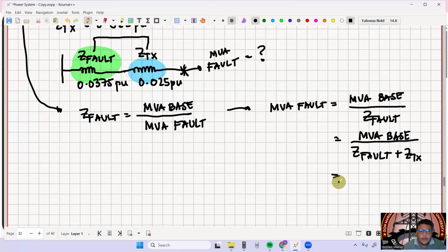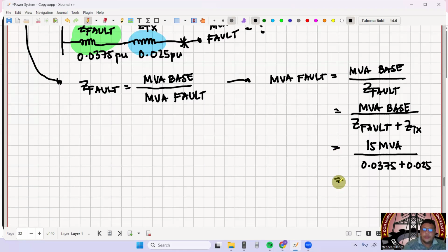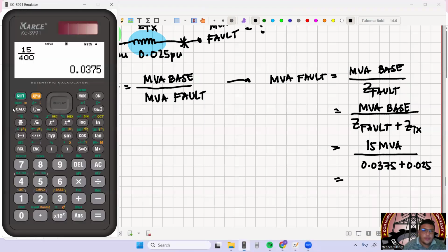So therefore this is now equal to 15 MVA all over 0.0375 plus 0.025. So therefore MVA fault na natin, or our new MVA fault, is what?